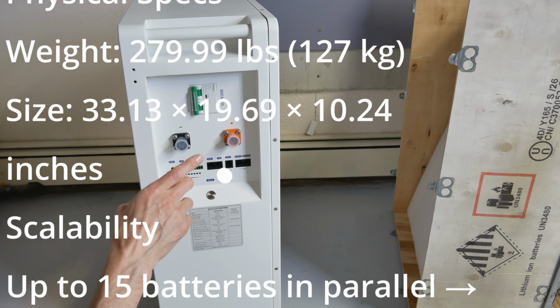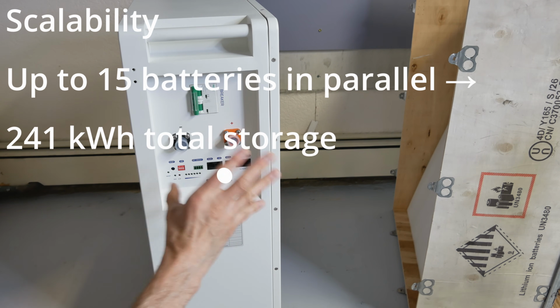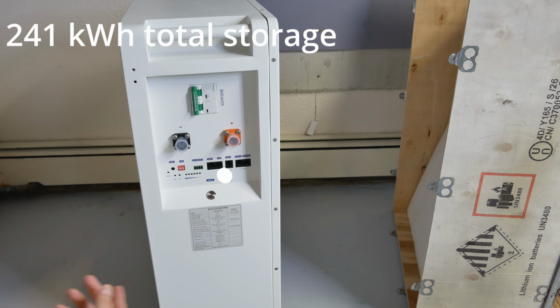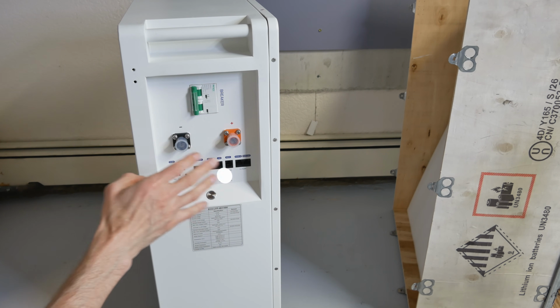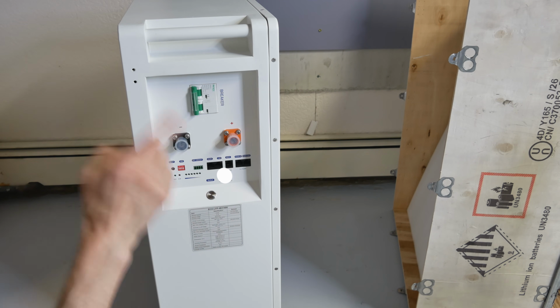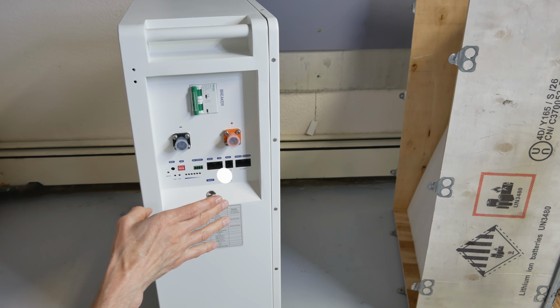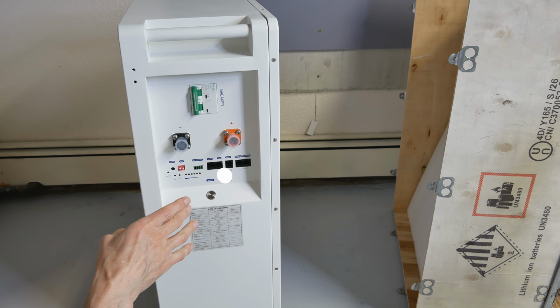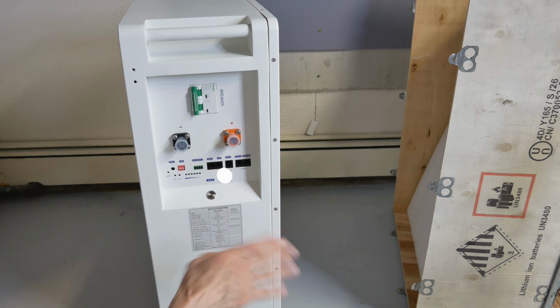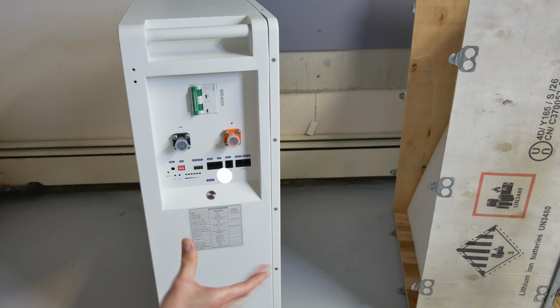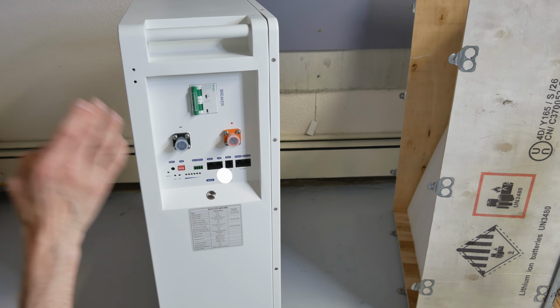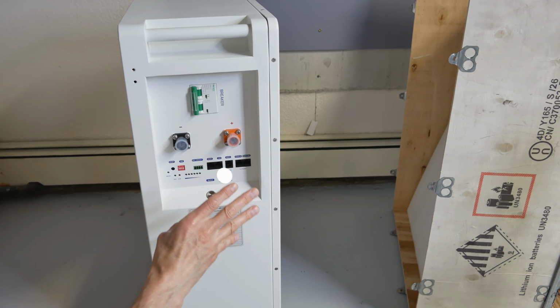Temperature ranges that it can function at range from 0 C to 55 C, and the discharge rate can function from -20 C to 55 C, which is a fairly wide range to be able to operate under. The scalability is truly epic with this system - you can put up to 15 batteries in parallel, up to 241 kilowatt-hours of total storage. You got that right, 241 kilowatts. This is basically whole-home backup territory with this alone. But if you scaled 2 to 3 of these together, you can go for days probably, depending on what your loads are and what you run in your house.